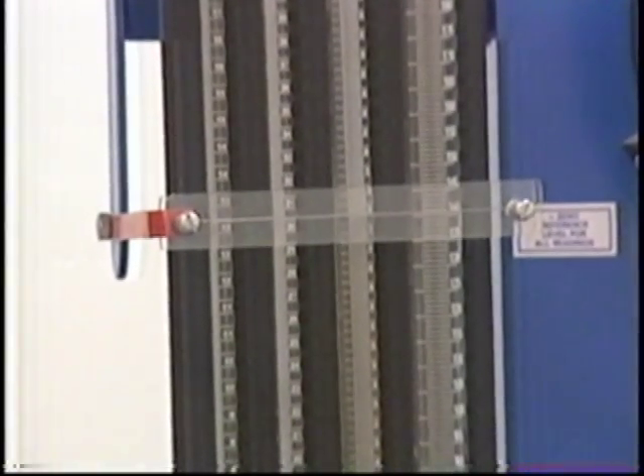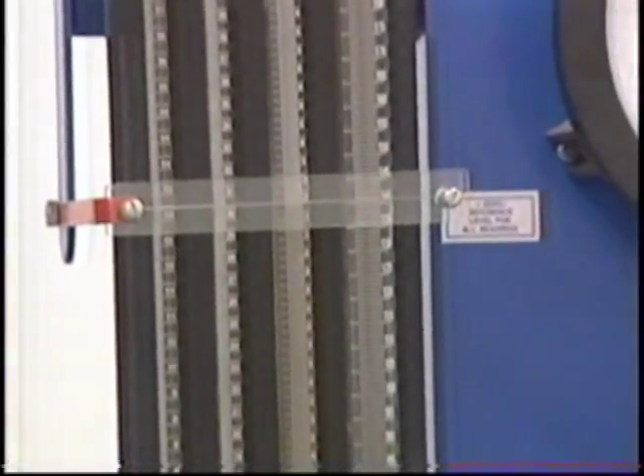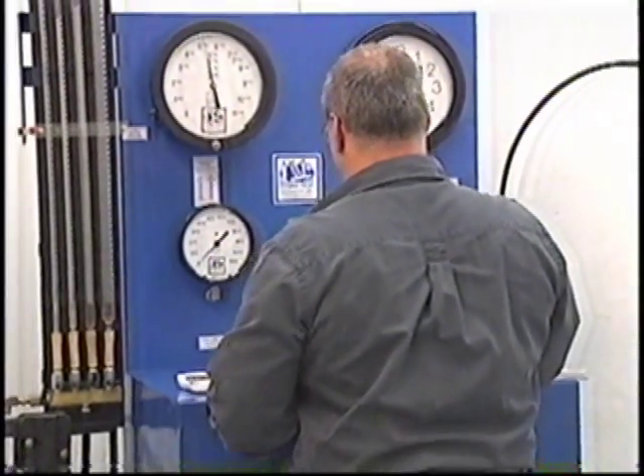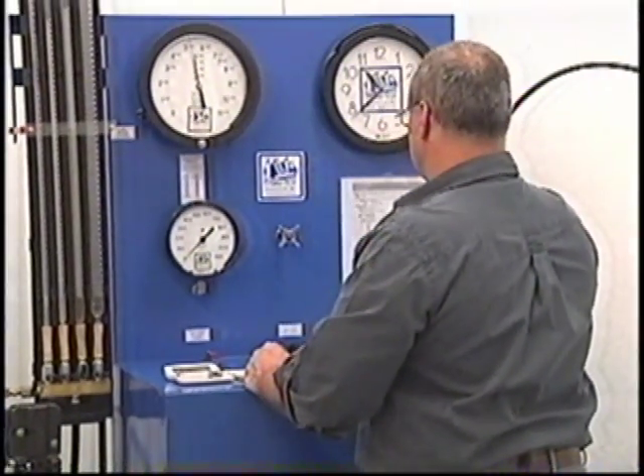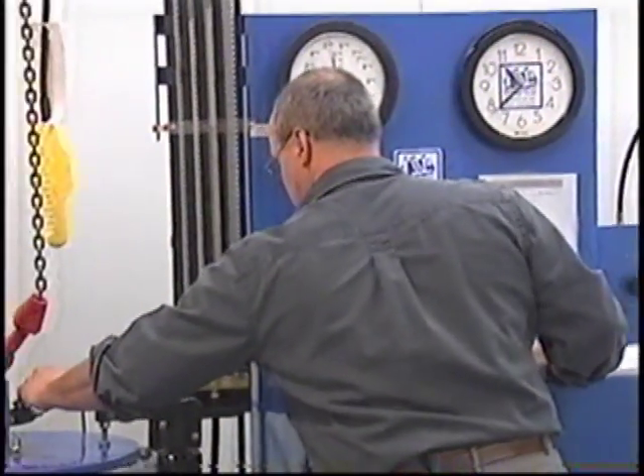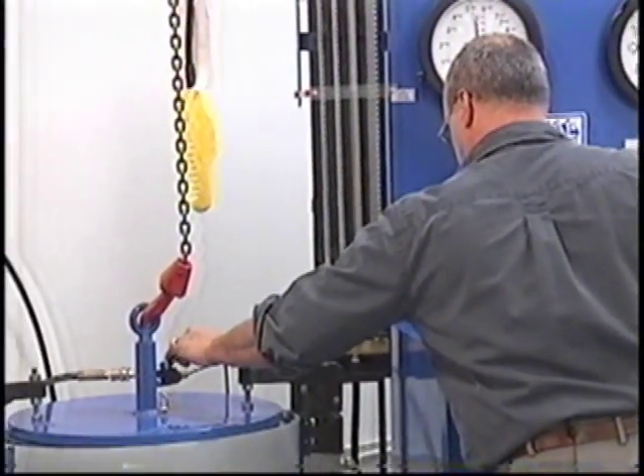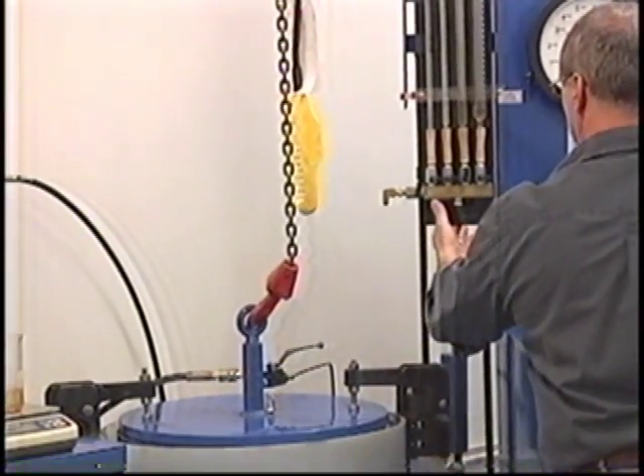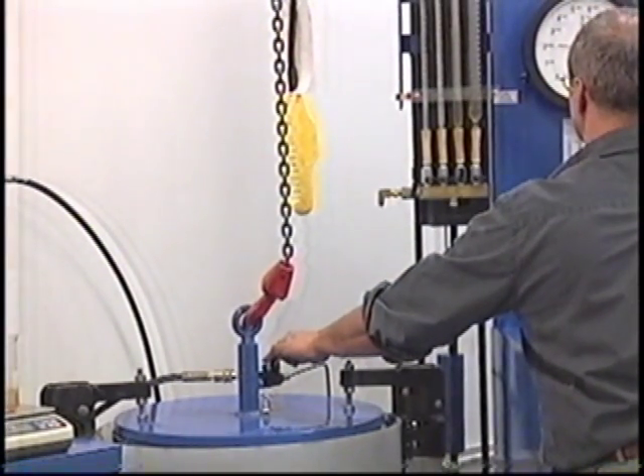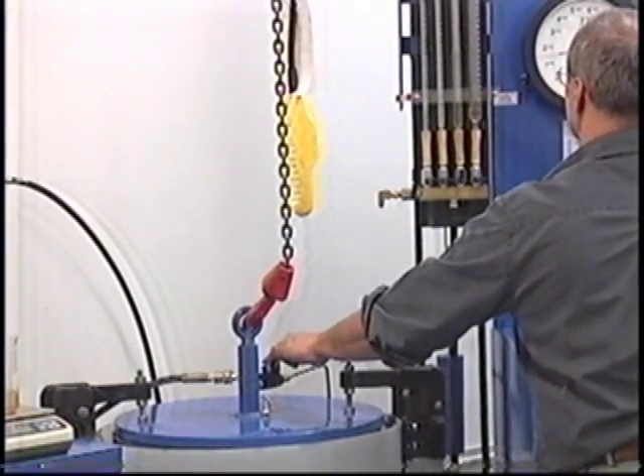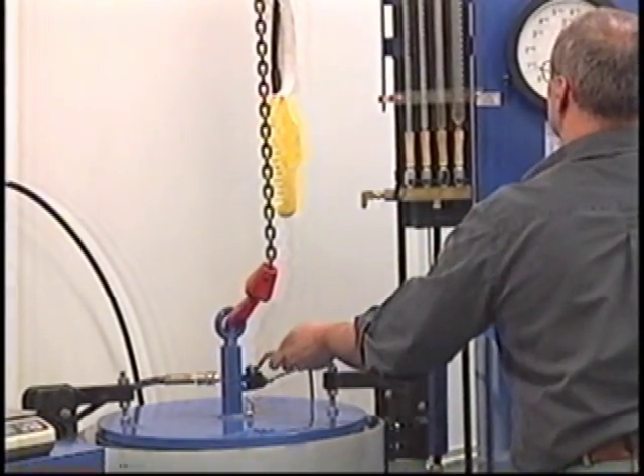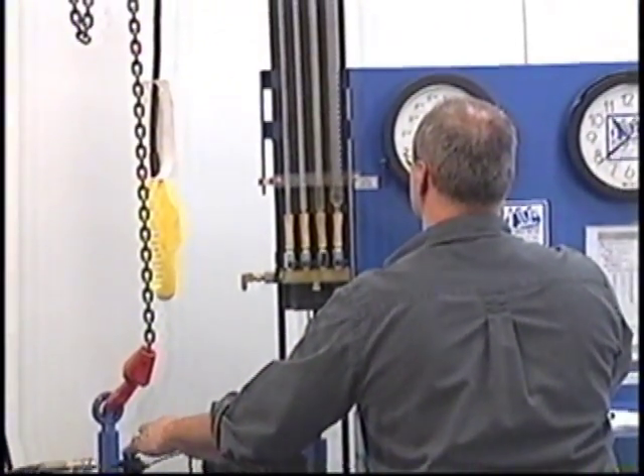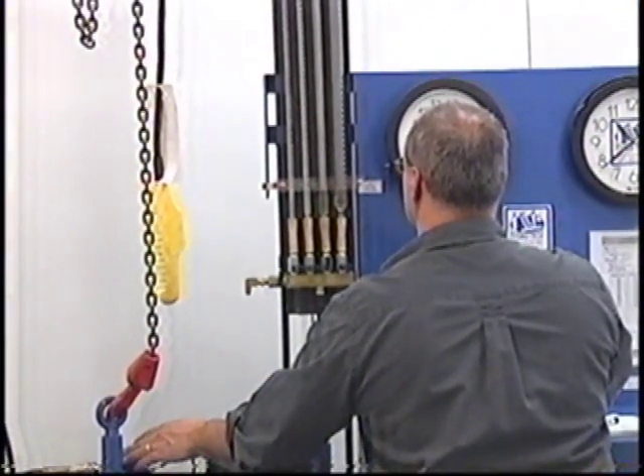In this case we went exactly to 5000, so that is the number that we will put in under the test pressure, and our total expansion was 73.4 cc. We are then going to relieve the pressure, and this will tell us what our permanent expansion is.